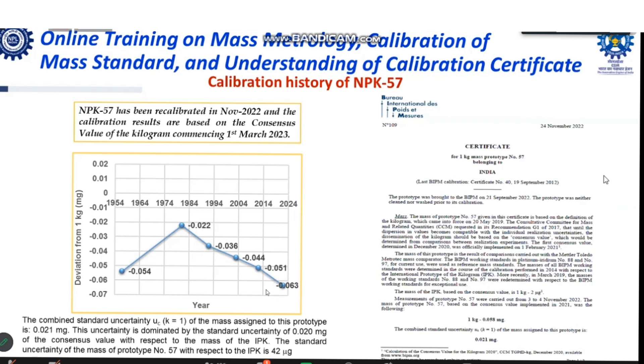The recent calibration gives a nominal value of 1 kg minus 0.063 mg. The combined uncertainty for the mass assigned to this prototype is 0.021 mg. This uncertainty is dominated by the standard uncertainty of 0.020 mg of the consensus value, so because we are getting the value from the consensus value, we also have to account for that measurement uncertainty of 0.020 mg.